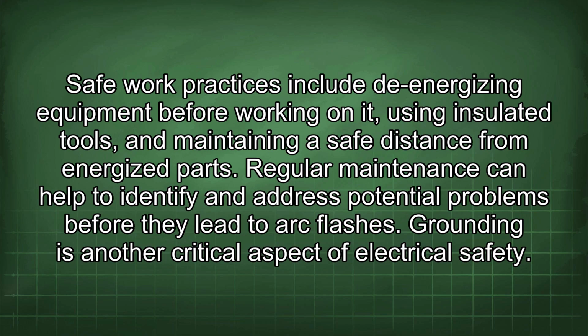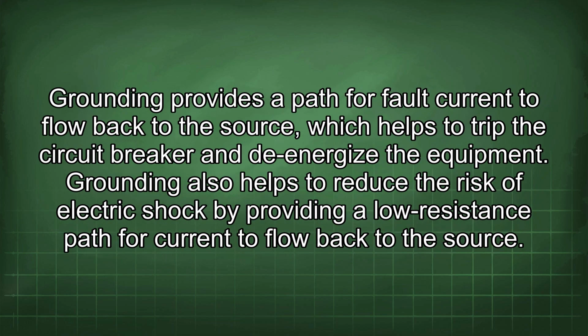Grounding is another critical aspect of electrical safety. Grounding provides a path for fault current to flow back to the source, which helps to trip the circuit breaker and de-energize the equipment. Grounding also helps to reduce the risk of electric shock by providing a low resistance path for current to flow back to the source.